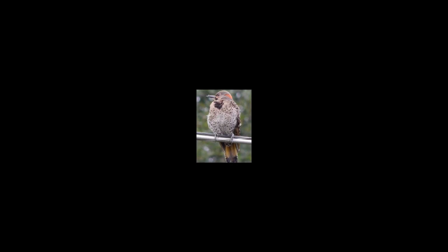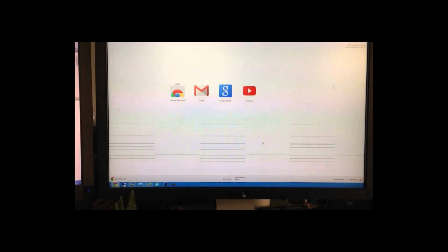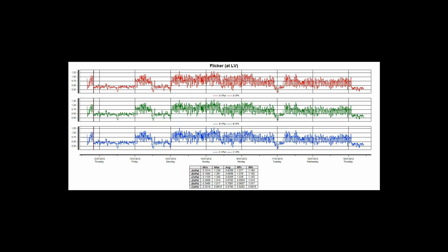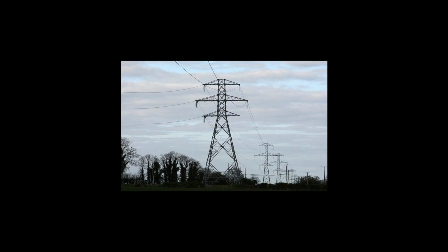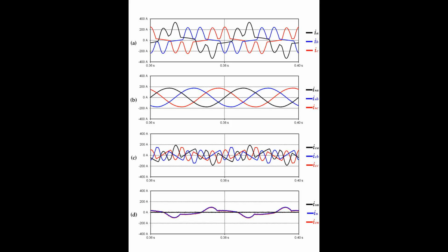Estimation. A purely analytical calculation of PST is almost impossible. In the standard there are formulas which allow the estimation of the PST values to be expected. Flicker mitigation. Flicker is generated by load changes. Only the amplitude of the load change is relevant, not the absolute value. A reduction in flicker can be attained through making less frequent load changes, or smaller load changes, if the load is changed gradually, for example, by the help of power electronics, instead of step fashion. This also makes flicker less perceptible.